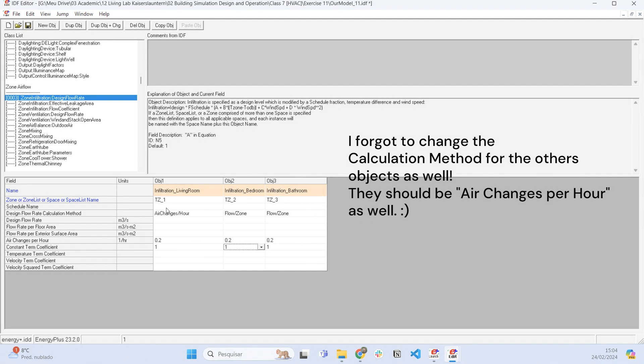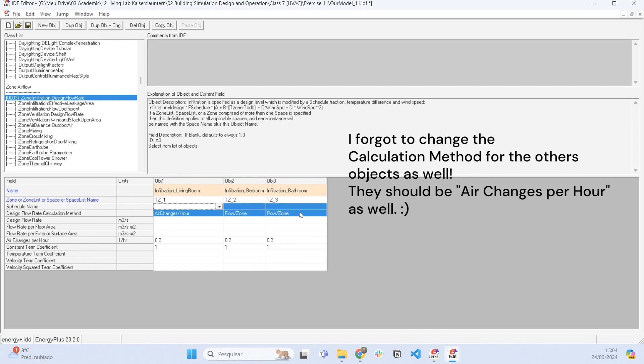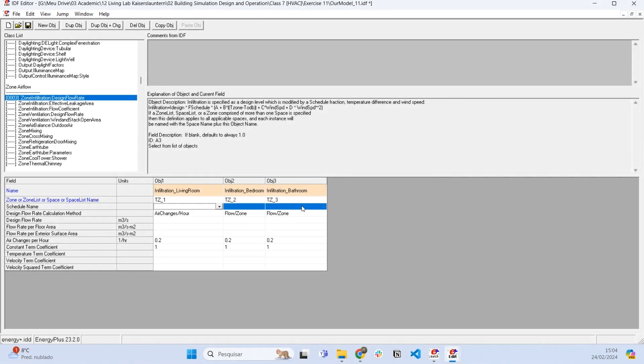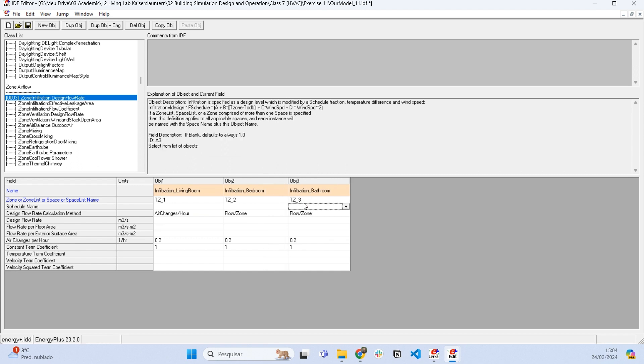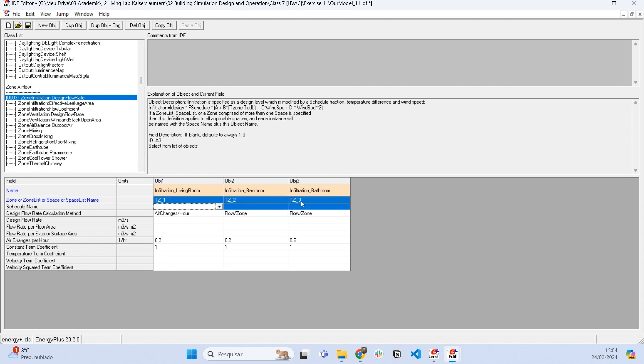What is missing here is the schedule name. We need to set a schedule of availability for the infiltration, otherwise there's going to be infiltration all the time. This doesn't happen in the real world because the infiltration is the opposite schedule of the air conditioning.